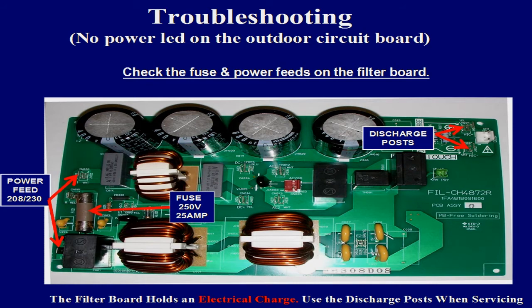The filter board is fed with 208/230 volts AC of input power. There is a cartridge type fuse rated at 25 amps at 250 volts AC, which fuses one side of this incoming power supply. Always check this fuse to verify continuity or 0 volts across it if power is applied.